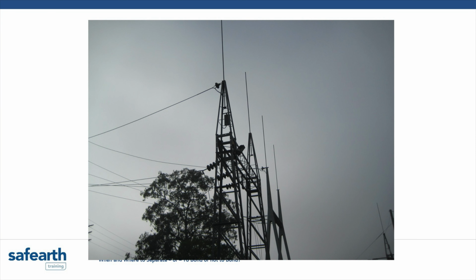Here's another of their systems where the earth wire lands on a disc insulator, and what's coming out and running down the gantry is not the earth wire, it's actually the pilot wires inside that old style of steel catenary earth wire. It's called Hardex, with 5 pilots in it, a pretty old system they don't tend to use anymore, but it created all sorts of problems.